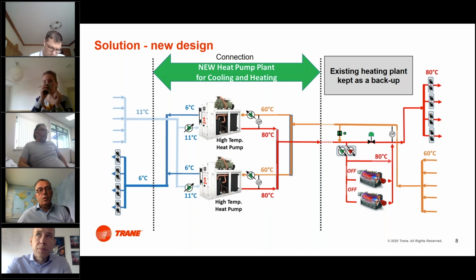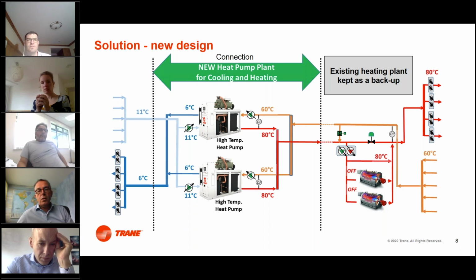And at summertime, when needed, these units can run as coolers only when it would really be needed. But we know from the load chart that there's always a need for heating in the same building. So the old system, or the boiler system, did not need to be replaced. We suggested to keep that as a backup. It always makes sense to keep this as a backup for two reasons. One is you never know when more heat is needed, and it doesn't take an investment to keep what you have.